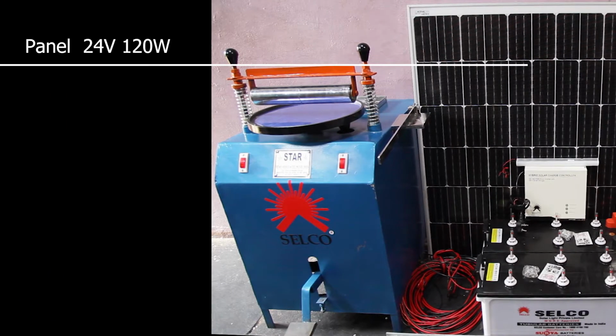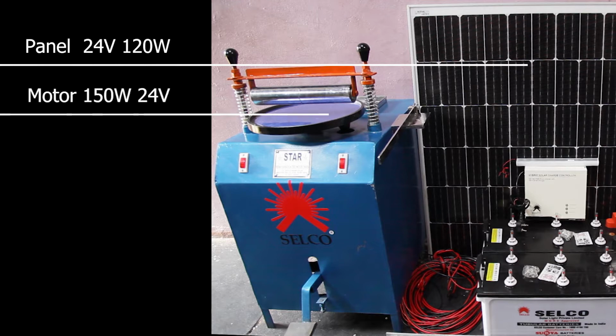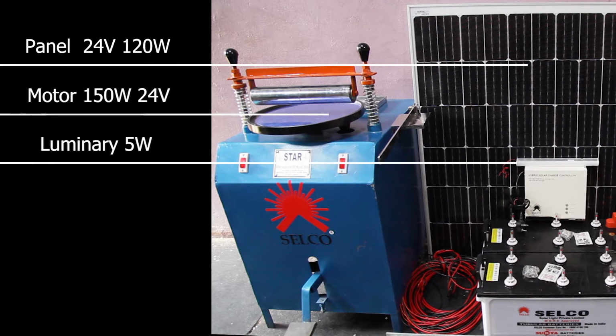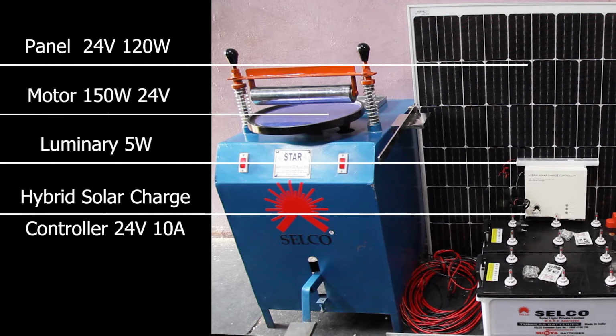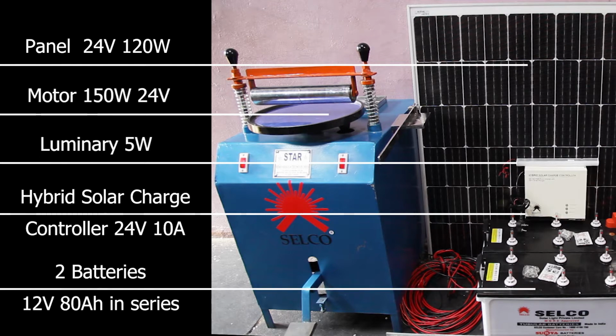Panel 24 volt 120 watt. Motor 150 watt 24 volt. Luminary 5 watt. Hybrid solar charge controller 24 volt 10 ampere PWM smart charger with 24 volt 4.5 ampere AC charger. 2 batteries 12 volt 80 ampere hour each connected in series.